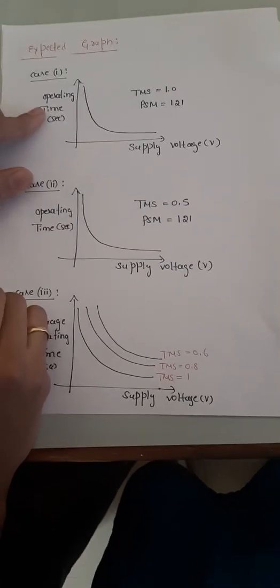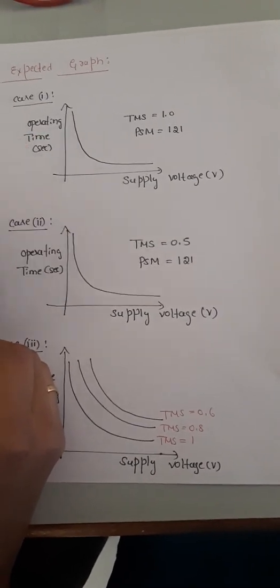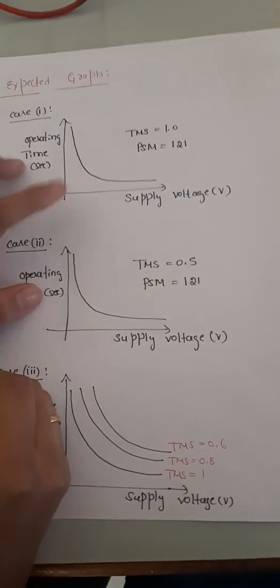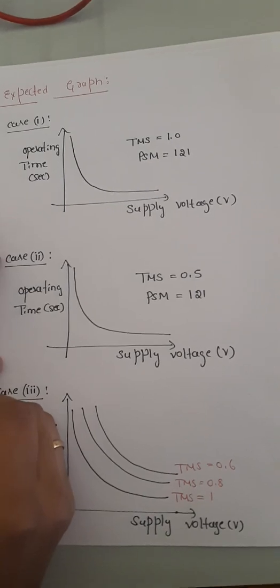From Cases 1 and 2 we plot a graph with supply voltage on the x-axis and operating time on the y-axis. The two curves are similar but the Case 2 times are half of Case 1. Both graphs exhibit IDMT (Inverse Definite Minimum Time) characteristics: at minimum supply voltage, operating time is maximum; as supply voltage increases, the time taken for the relay to trip decreases.